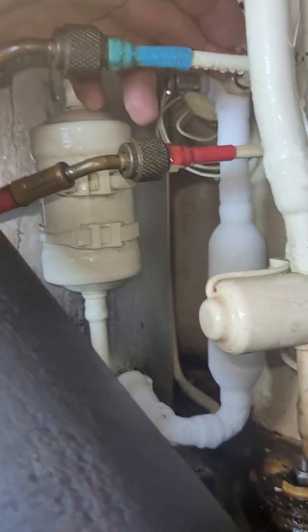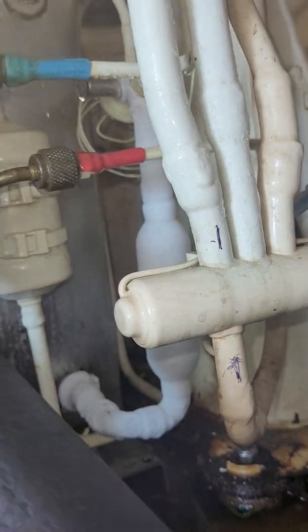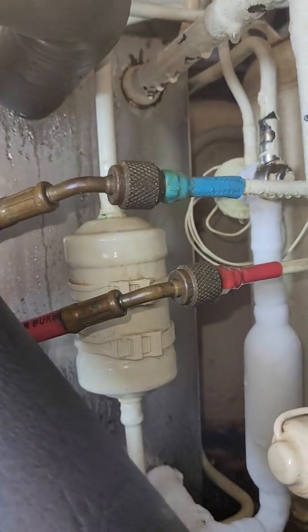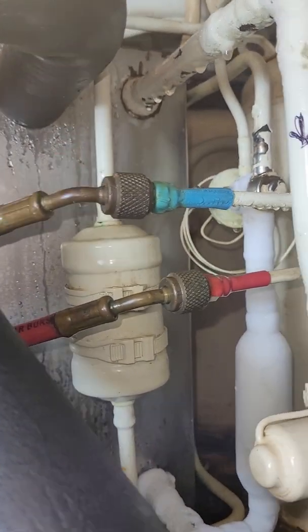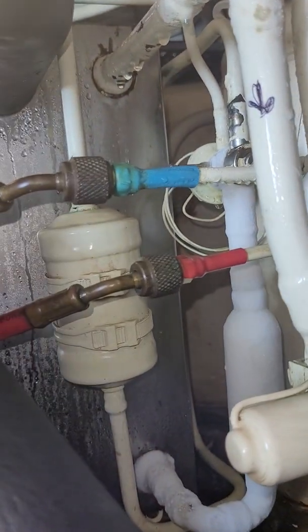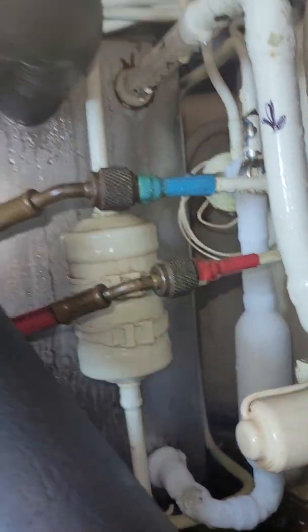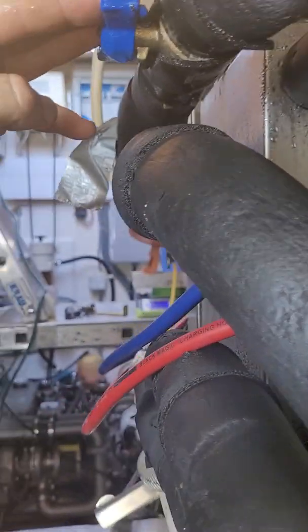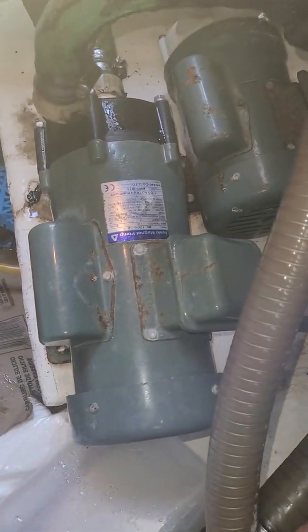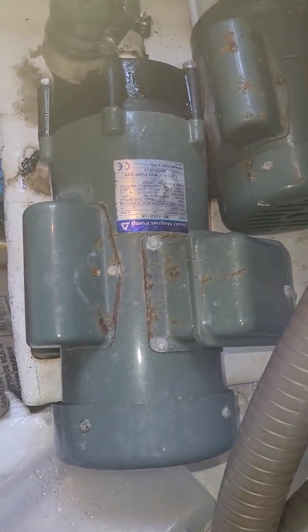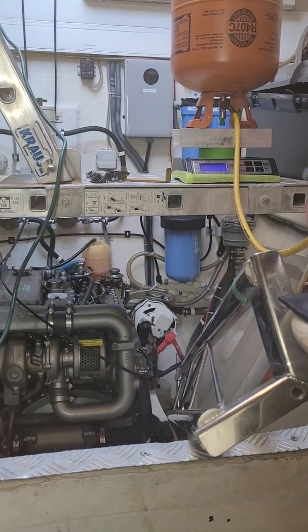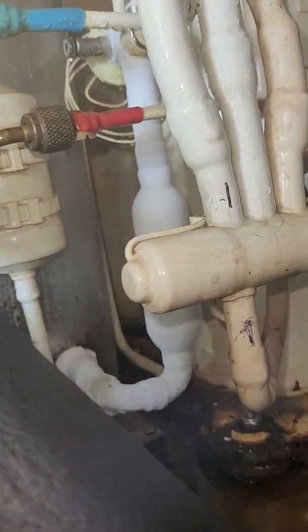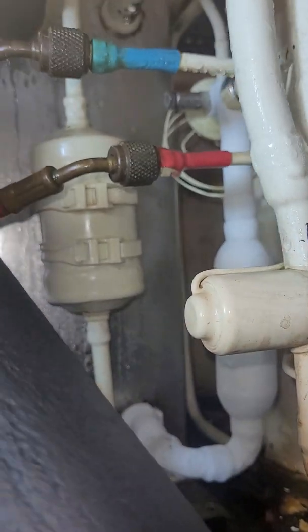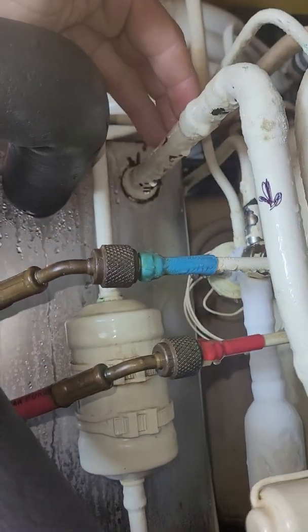What happens then is the expansion valve. It goes down and it goes into the heat exchanger. In this box, that's the heat exchanger, this stainless box. What happens in there is the refrigerant absorbs the heat, which gets transported there through the cold water. So down here you have the circulation pump. This is the chilled water circulation pump. That's the raw water pump. We still have our tank set up there on the scale. So down here it's coming in at sub-freezing temperatures. The gas expands, goes into the heat exchanger, and up here it comes back up.